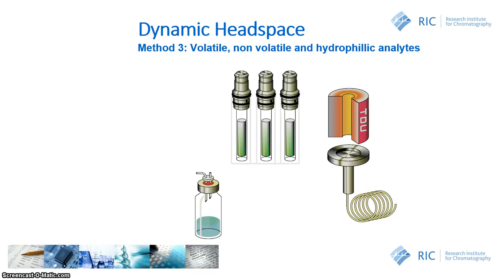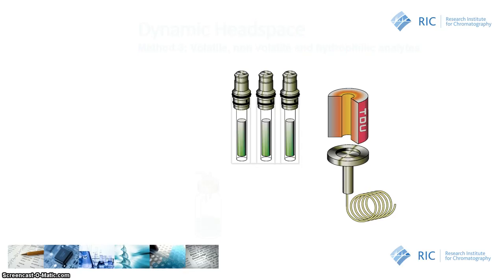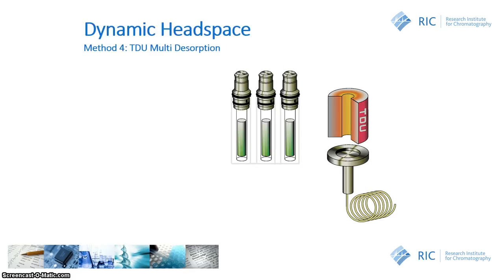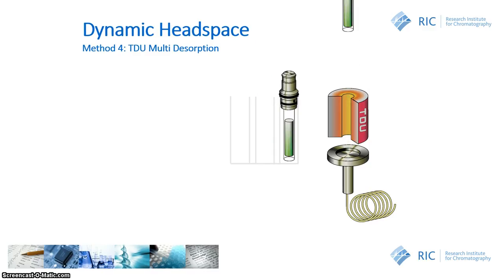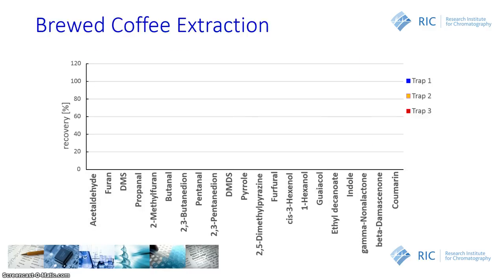After the dynamic headspace sampling, each tube is desorbed in the TDU in sequential mode. First the first tube is placed and desorbed, then while keeping the CIS cold, the second and third tubes are also desorbed. This is what we call the TDU multi-desorption mode.